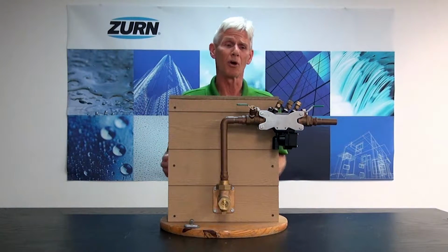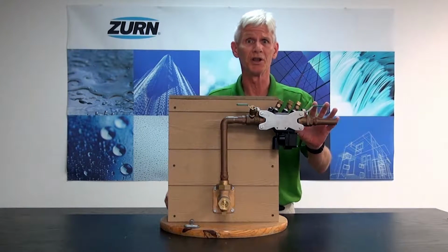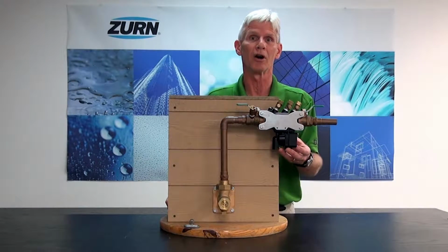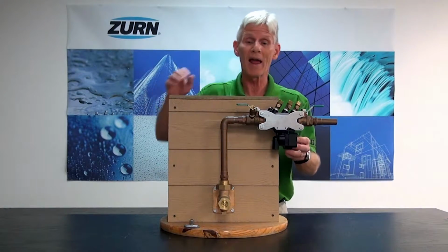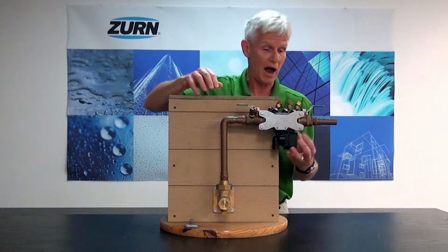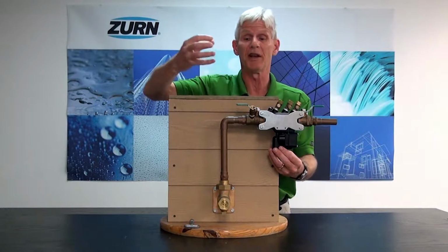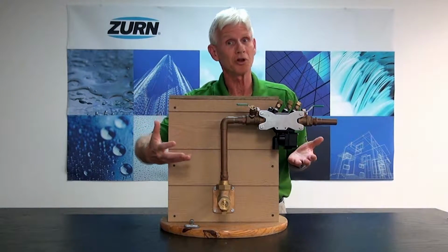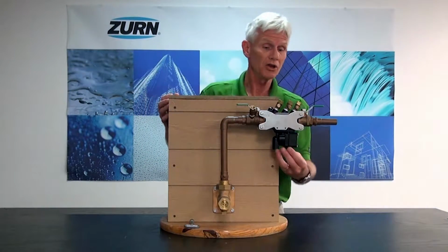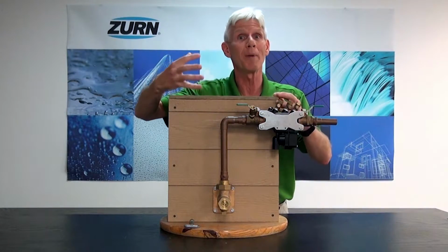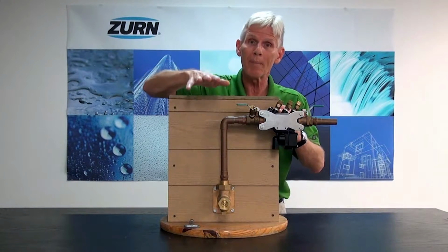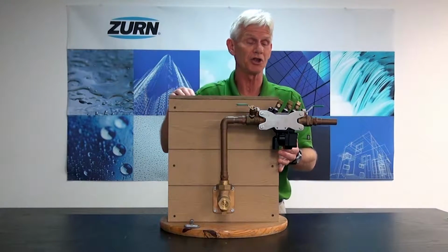Now before we do so, I want to point out that there are natural conditions that can make the relief valve discharge. That's what the backflow preventer is for, and that's what it's supposed to do. Whenever I have a drop of inlet pressure, I can have relief valve discharge. Basically, as the inlet pressure drops, I'm starting to approach a backflow condition, so the relief valve will discharge, trying to reestablish a differential in order to make backflow not occur. So a drop of inlet pressure can lead to relief valve discharge.